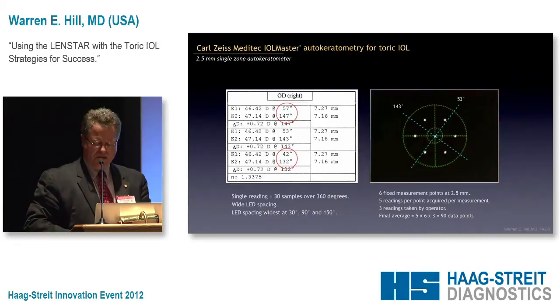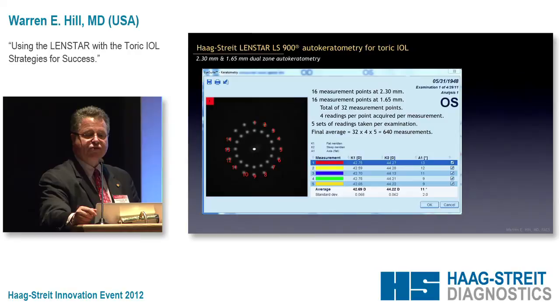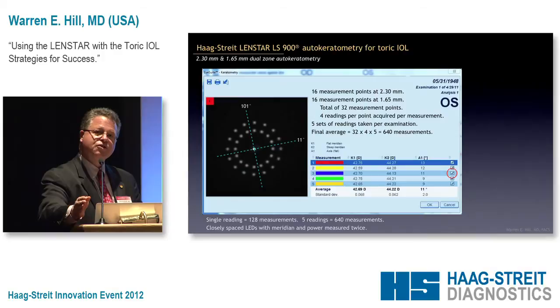Here's the Lenstar. You can see just from the reflected image off the case that it has a much higher density of measurements — not only that, but it measures twice. We have one ring of 16 measurements and another ring of 16, that's 32 measurements total. If we look at measurement number three, there's the steep and flat meridians — the measurements are much, much closer. There's almost no iteration that has to be done, and the chance of the steep meridian lining up with the area of measurement is very, very high.